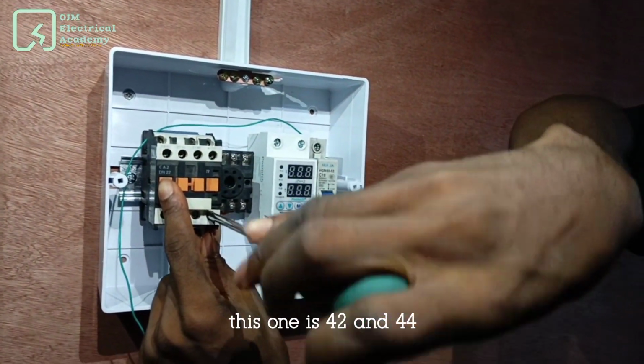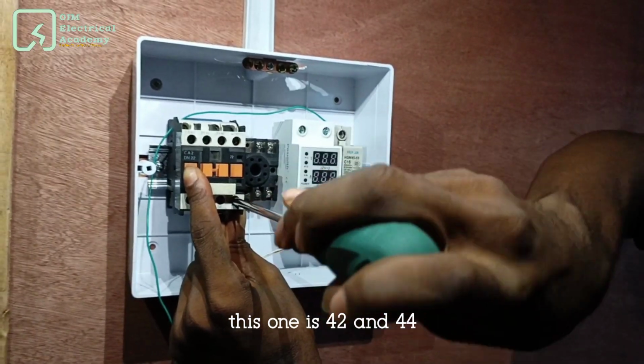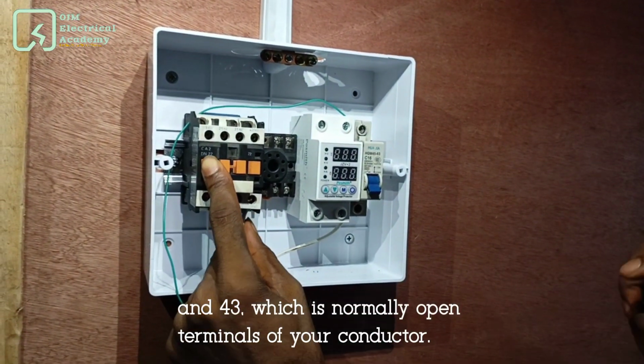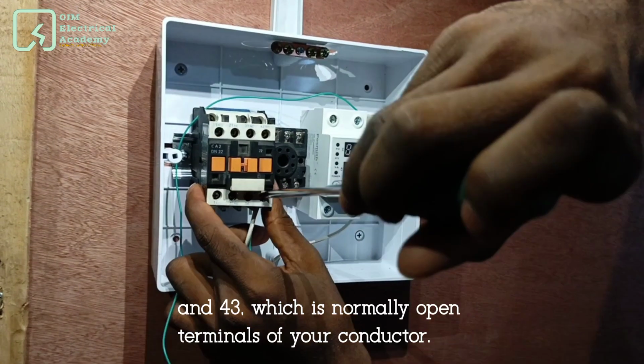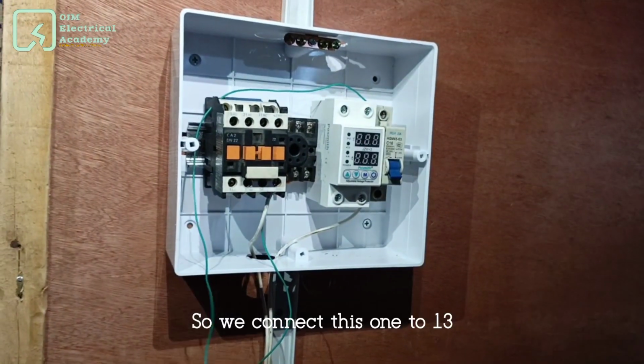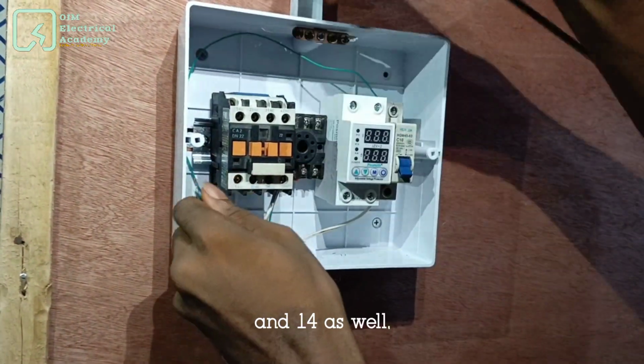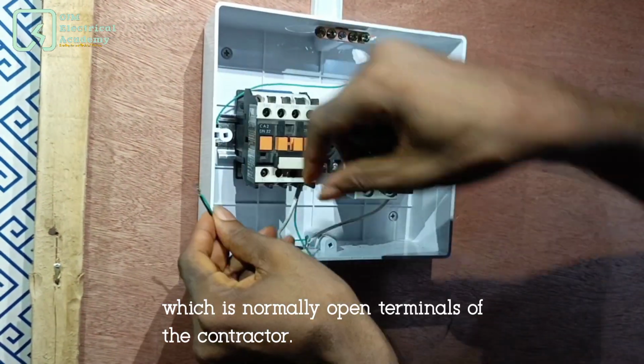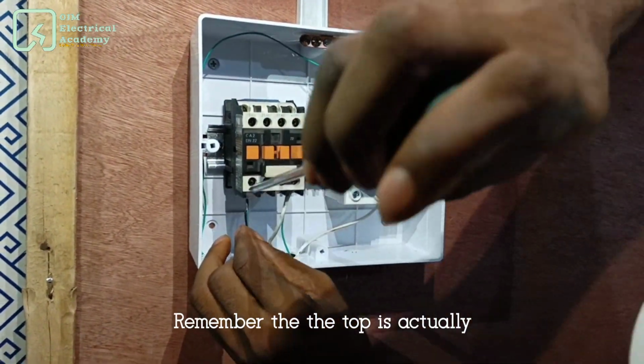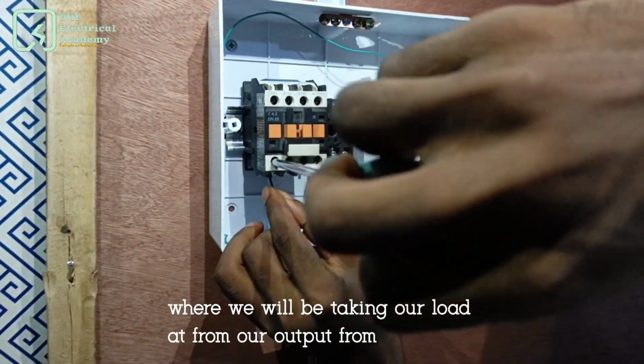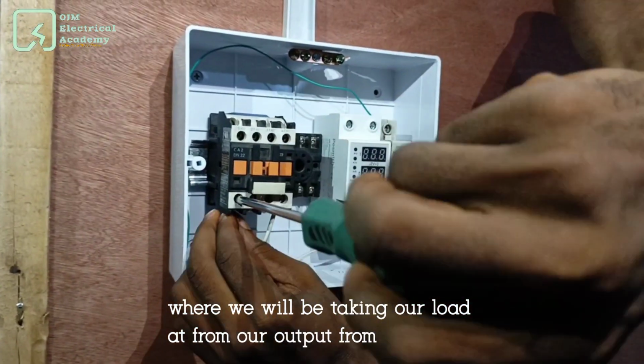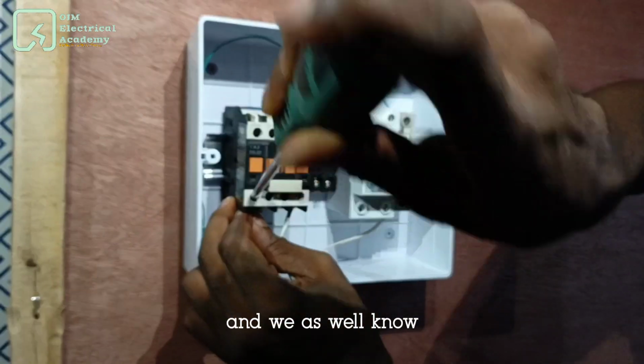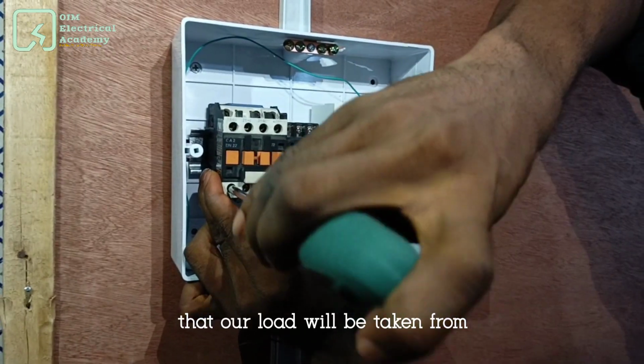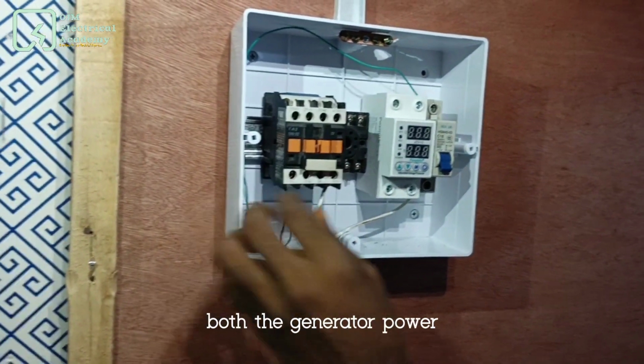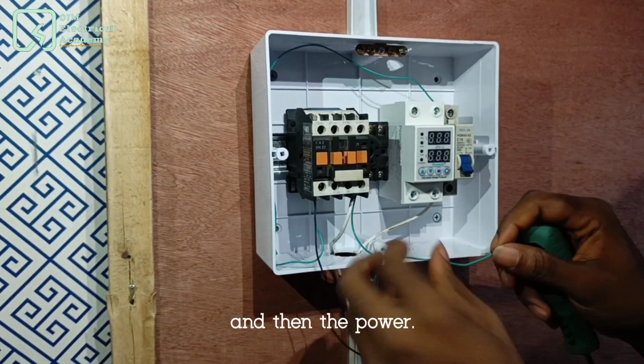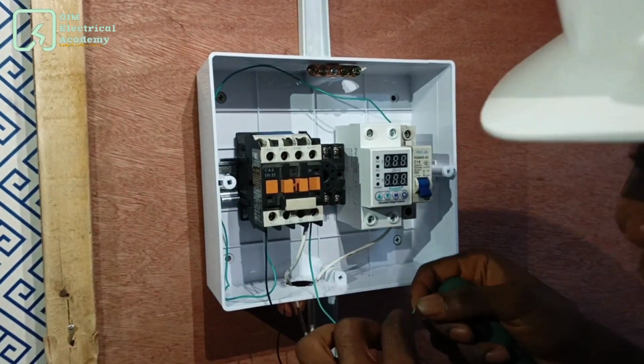13 and 14, this one is 44 and 43, which are normally open terminals of a contactor. So we'll connect this one to 13 and 14 as well. Remember, the top is actually where we will be taking our output from. And we know that our load will be taken from both the generator power and the NEPA power.